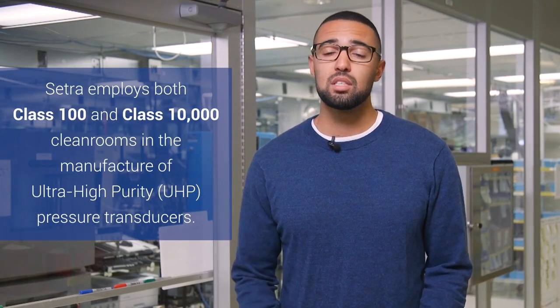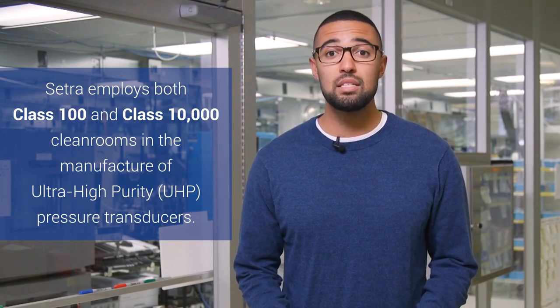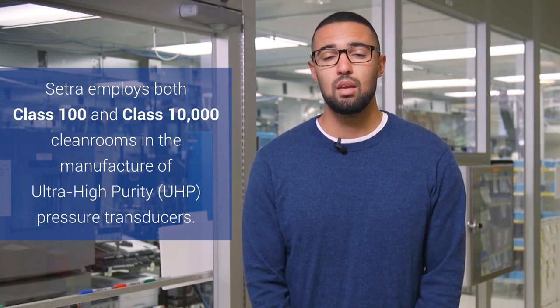How do you know your clean room is in fact clean? Industrial manufacturing clean rooms like the one behind me must closely monitor differential pressure, temperature, and humidity to prevent defects in products being made. Other clean room environments like pharmacies that do compounded sterile processing can be even more stringent in how they monitor their environments. But did you know even the strictest regulations for compounded pharmacies only require particle counts to happen twice a year? A lot can happen in between — so what do you do about the other 363 days of the year?